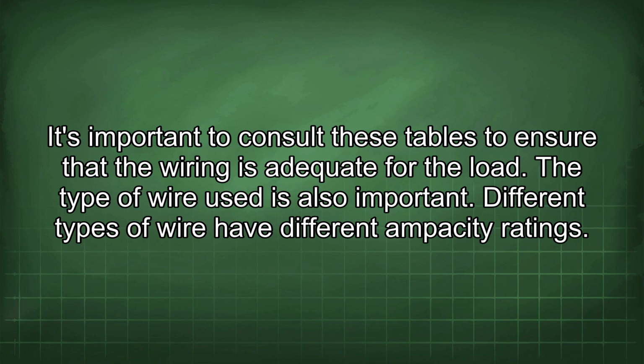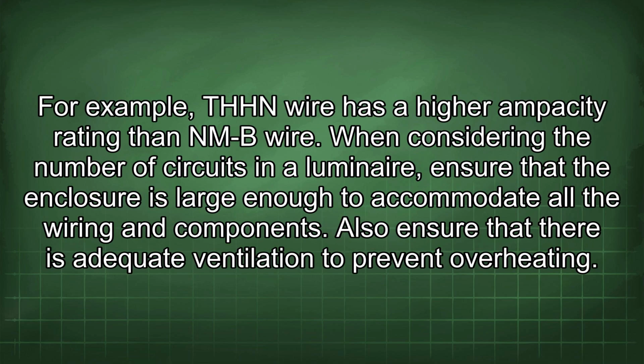The type of wire used is also important. Different types of wire have different ampacity ratings. For example, THHN wire has a higher ampacity rating than NMB wire. When considering the number of circuits in a luminaire, ensure that the enclosure is large enough to accommodate all the wiring and components. Also ensure that there is adequate ventilation to prevent overheating.